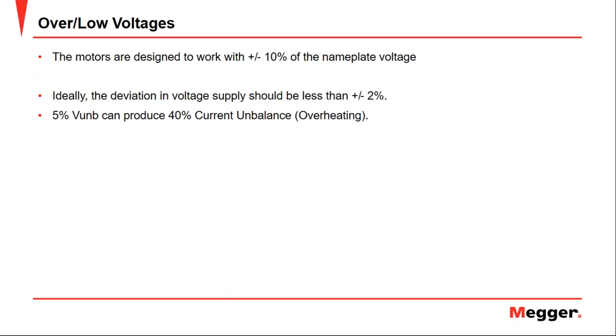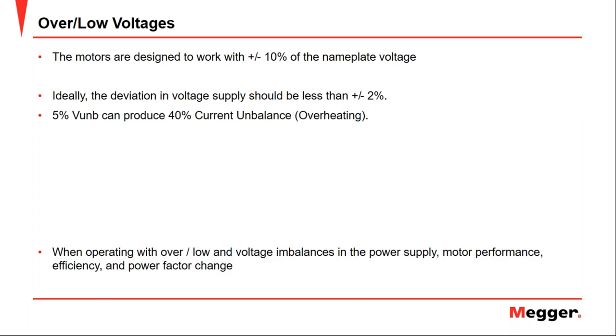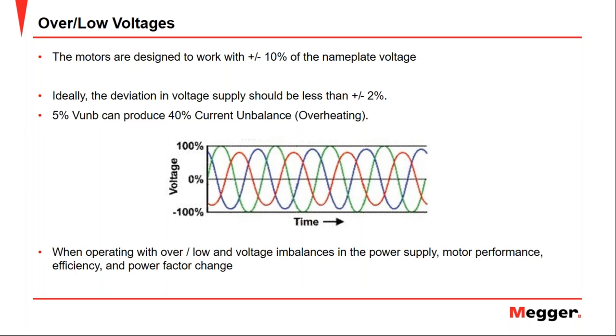This variation in the power supply most of the time makes the motor operate too hot. According to the OEMs, the motors are designed to work with plus or minus 10% of the nameplate voltage. And the standard indicates that deviation in the voltage supply should always be less than plus or minus 2%. We have to know that the variation in the voltage produces changes in the motor performance. The voltage is the most important variable in the power supply of the motor. We have to measure the voltage frequently in order to be sure that these values are within the limits established in the NEMA MG1.